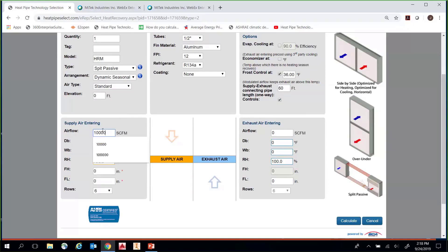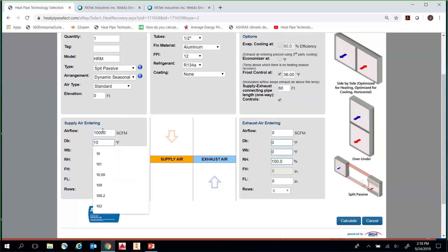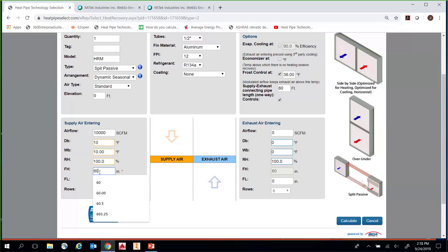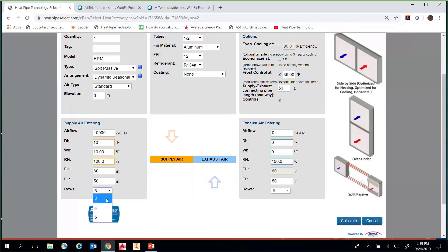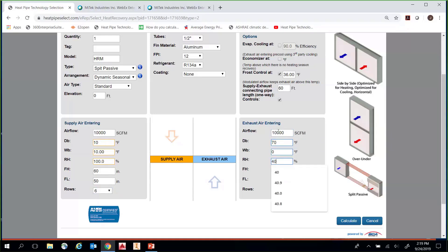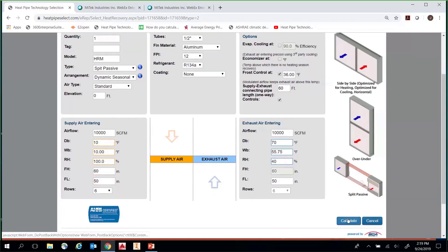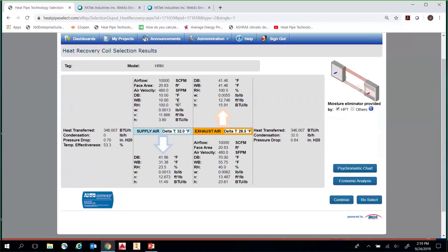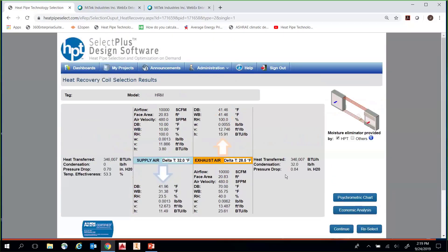I'm doing a 10,000 CFM system with winter conditions: 10°F dry bulb and 10°F wet bulb. I'm going to set fin height to 60 inches — that's our max per section; anything above that, Select Plus breaks it into two sections. And fin length at 50 inches. Rows can be two, four, or six. For the exhaust side, 10,000 CFM, 70°F dry bulb, 40% RH. After calculating, the results screen shows 53.3% effectiveness and pressure drop on the right-hand side, along with delta T for supply and exhaust.